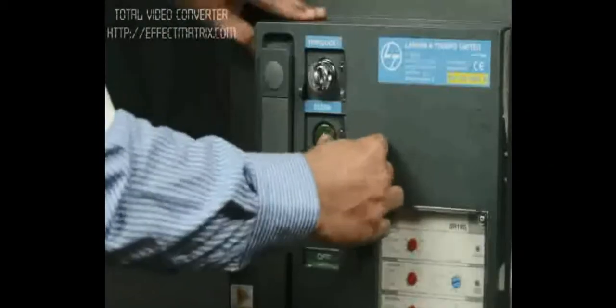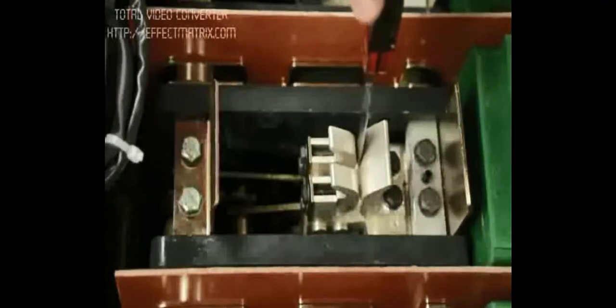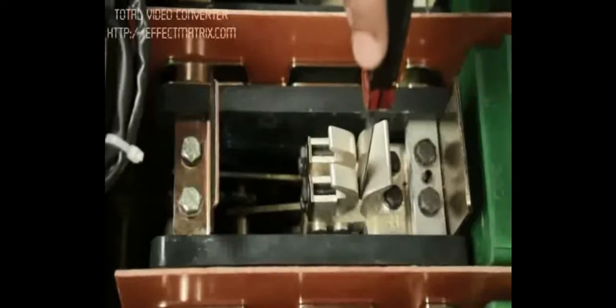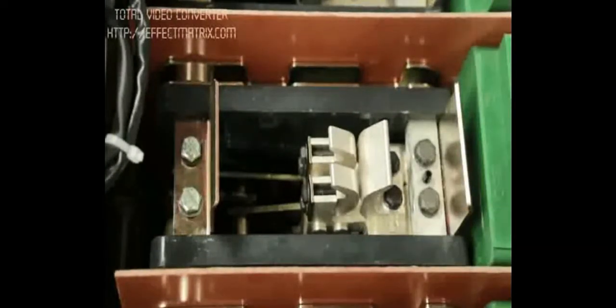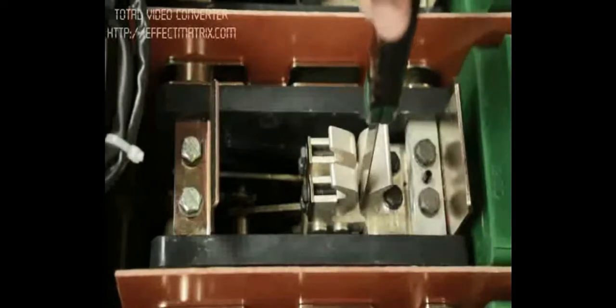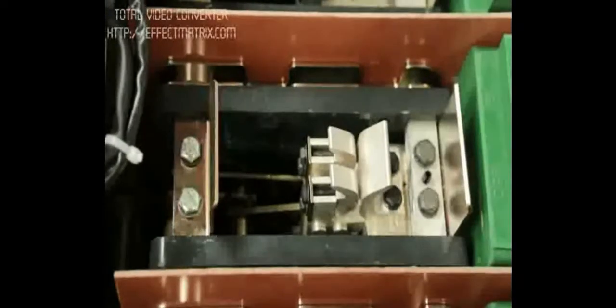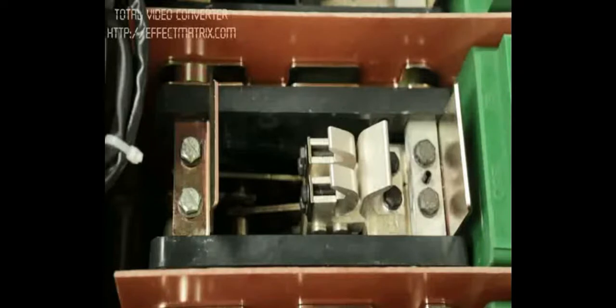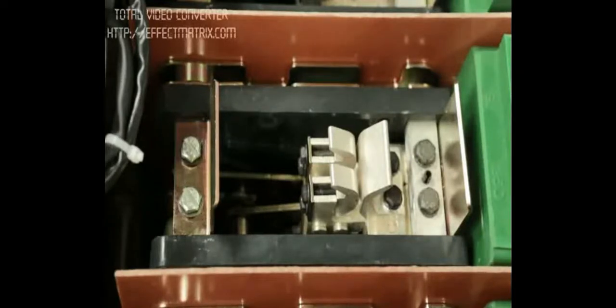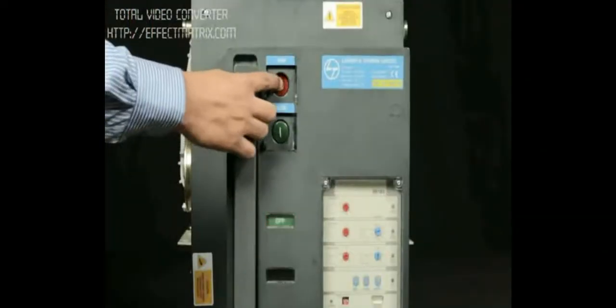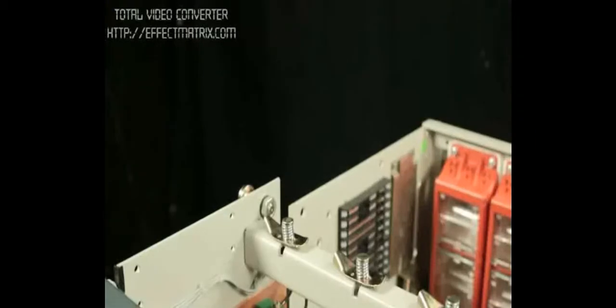Close it with the help of closing push button. Check gap between fixed and moving contact with the help of gauge. The gap should be 0.9 plus or minus 0.1 mm. If the gap is not correct, loosen the fixed arcing contact, adjust gap and tighten again with the help of ratchet. Now trip the ACB. Place arc chute on the top of the pole.